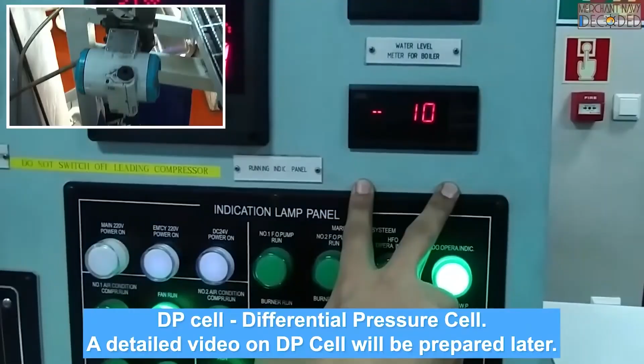Is the burner motor running or not? Is the feed water pump for the boiler running or not? So all the indications for the boiler system I get in the ECR itself, apart from the alarms. The water level I am getting remotely is through a DP cell, differential pressure cell. It measures the differential pressure in the steam drum and lets us know the water level remotely.